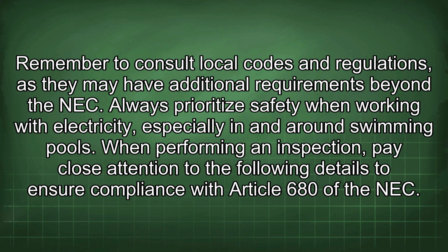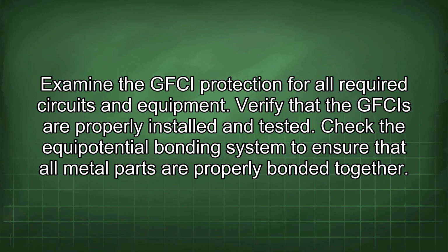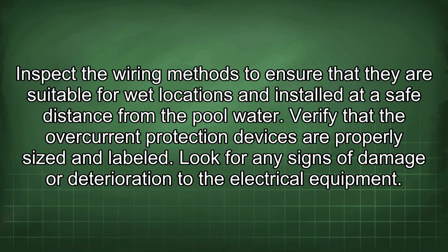When performing an inspection, pay close attention to the following details to ensure compliance with Article 680 of the NEC. Examine the GFCI protection for all required circuits and equipment. Verify that the GFCIs are properly installed and tested. Check the equipotential bonding system to ensure that all metal parts are properly bonded together. Inspect the wiring methods to ensure that they are suitable for wet locations and installed at a safe distance from the pool water. Verify that the overcurrent protection devices are properly sized and labeled.